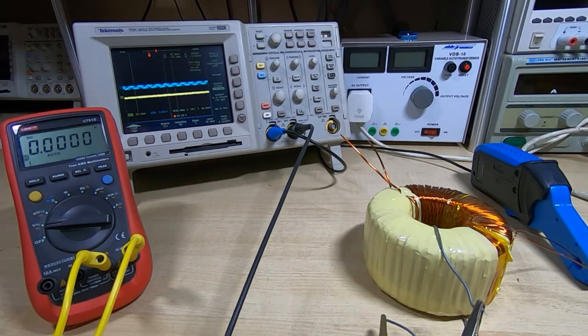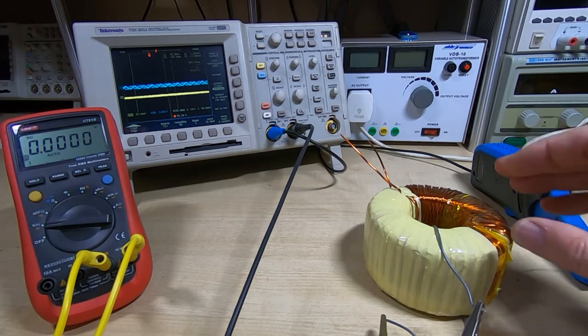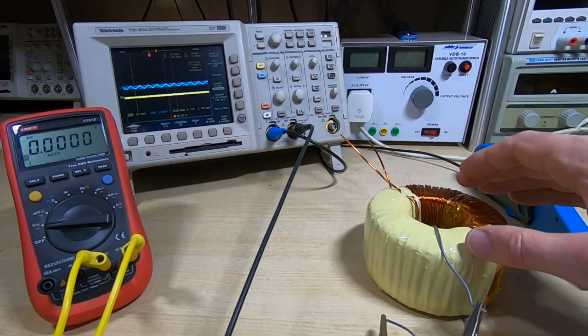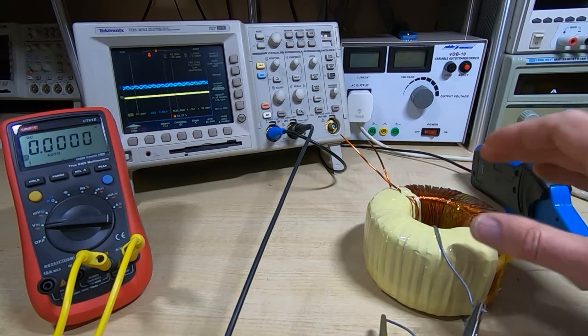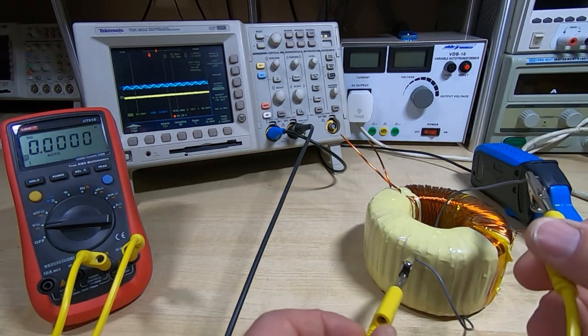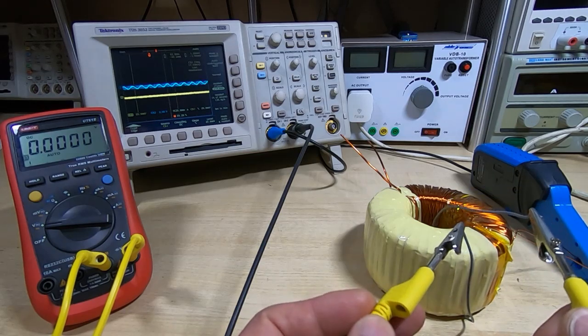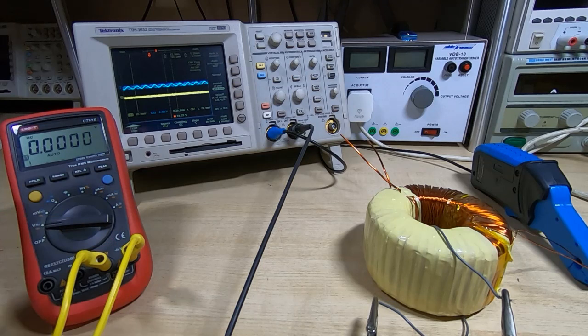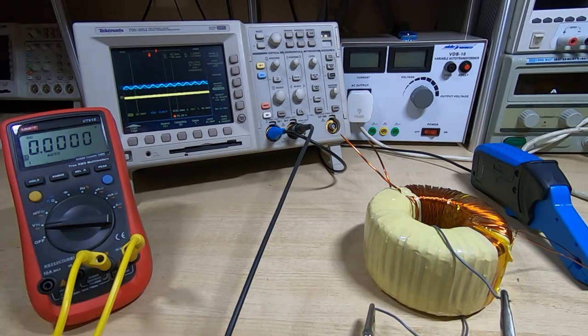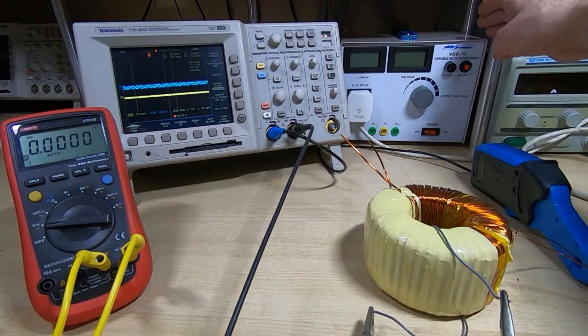If you're fairly certain it's a power transformer and you can identify which are the secondaries and which are the primaries, then you can do some very rough and ready testing. We'll determine the number of turns on the primary winding. The easiest way is to put a single extra turn around the core.